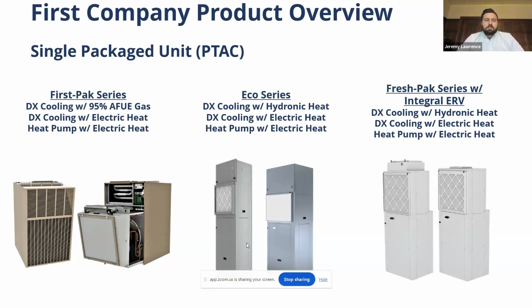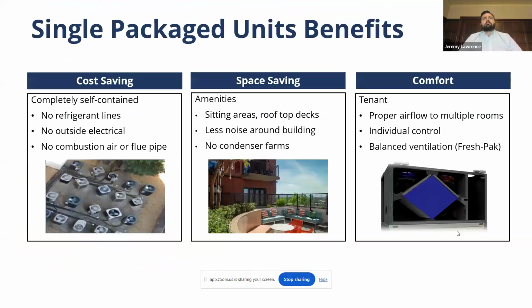New to this series is the First Pack, which is a high efficiency gas unit, and the Fresh Pack series with an integral ERV built right in. So Fresh Pack essentially comes off the basis of the Eco with the ERV built in as well. So PTAC units, as we kind of talked about, they are an all-in-one. They fit in a sleeve. They do need to be on an outside wall so that they can exchange air through the condenser, but they're all contained within one space.